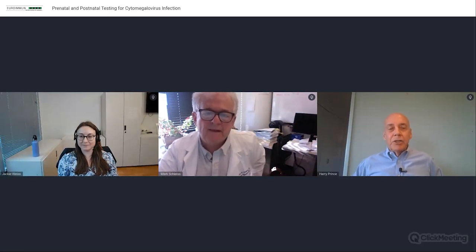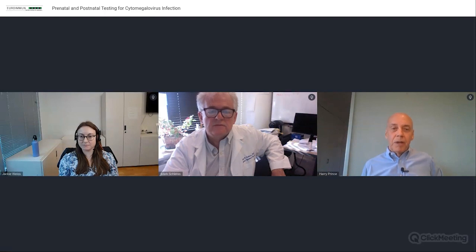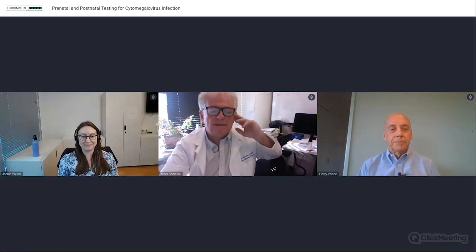If that isn't possible, there's a couple of other alternative approaches you can take. A sample that is IgG positive but IgM negative, with the extremely rare exception, is going to have high avidity. So those would be your high avidity group. And as I mentioned, if you have samples that are IgG positive and IgM positive with a really, really strong IgM signal, the vast majority of those, if not 100%, are going to be low avidity. So those two samples could be used in your testing to set your cutoffs between low, intermediate, and high avidity.